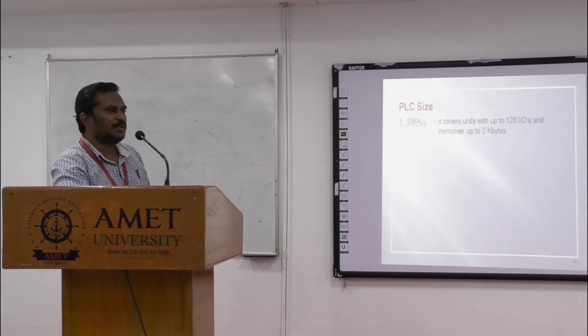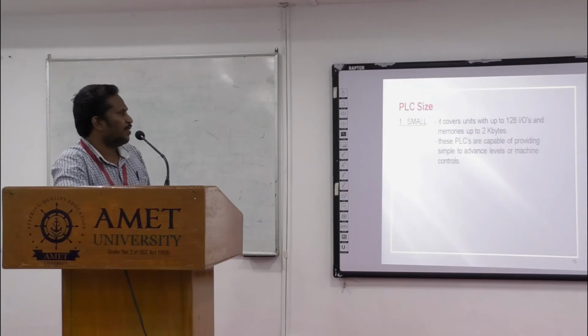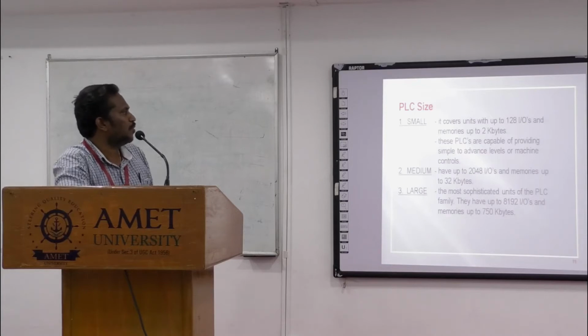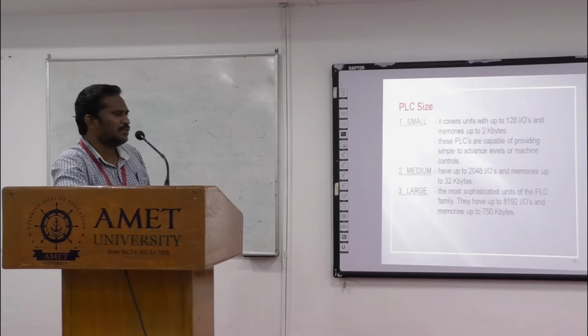PLC size depends upon the application. PLC sizes vary, and small, medium and large PLCs are available. Small PLCs cover units with up to 128 inputs and outputs and memories up to 2 kilobytes. These PLCs are capable of providing simple to advanced levels of machine control. Medium PLCs have up to 2048 input outputs and memories up to 32 kilobytes. Large PLCs, the most sophisticated units of the PLC family, have up to 8192 input outputs and memories up to 750 kilobytes.